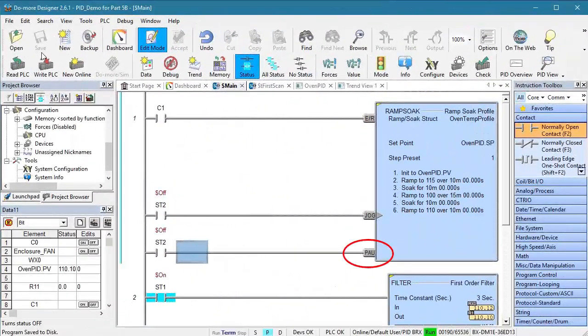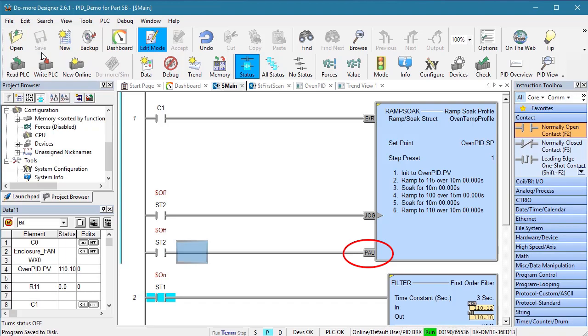Now the pause control simply tells the instruction to freeze execution at the current step until pause is released. Jog is edge triggered as indicated by the gray triangle. Each time you toggle jog, the ramp soak will immediately exit the current step and move to the next step in the table.